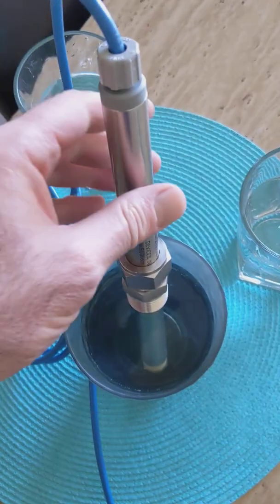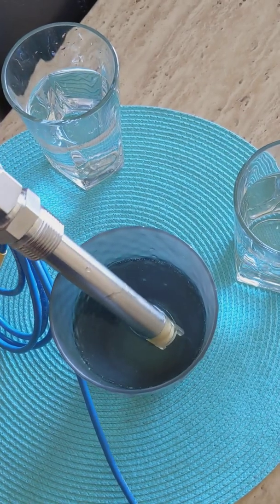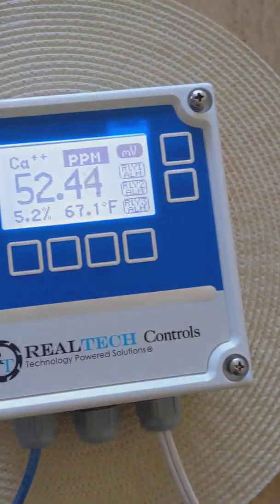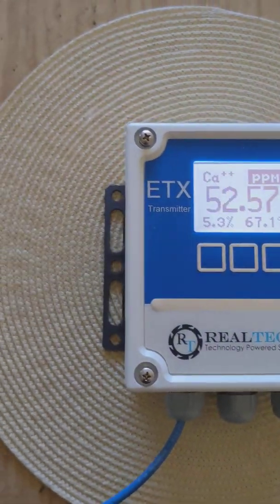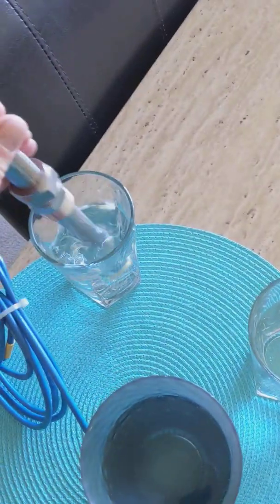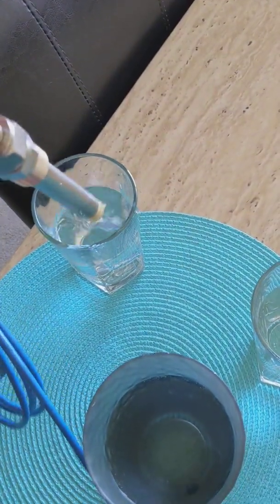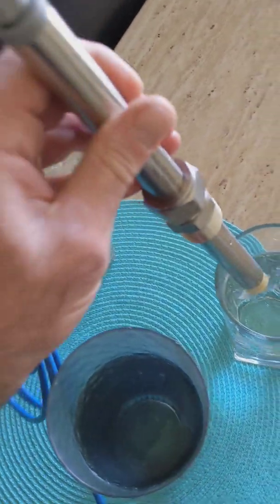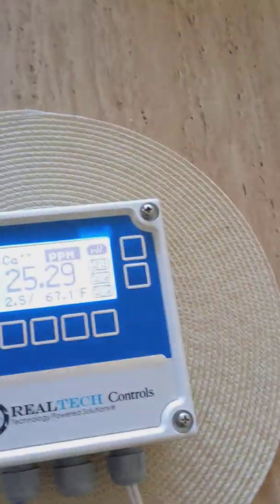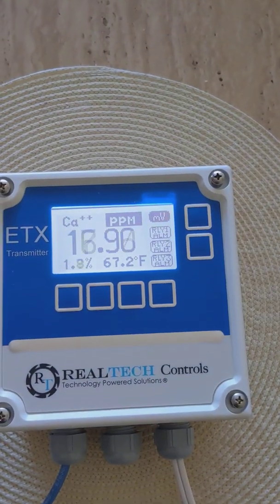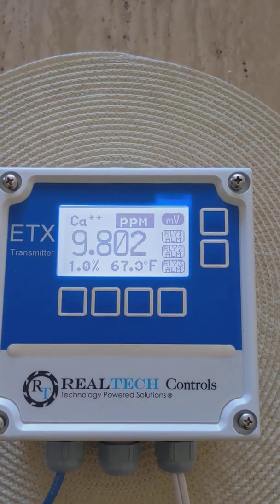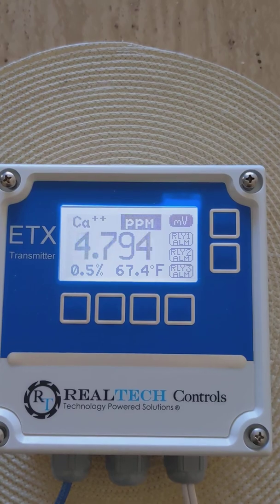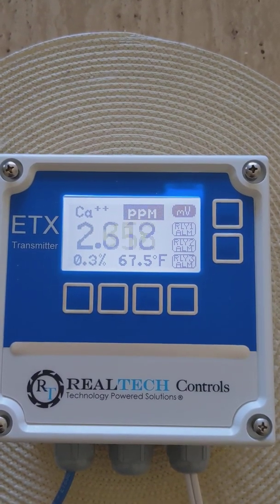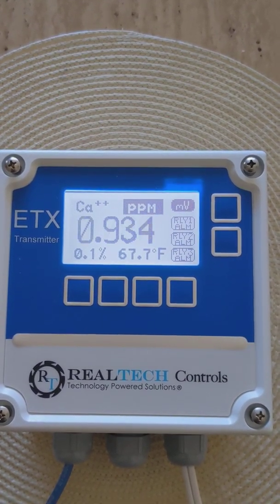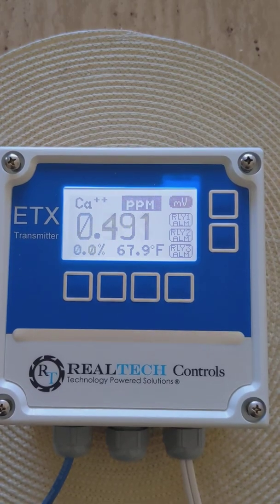I have my water hardness analyzer in city water, and it's reading 52 ppm. I'm now going to put it in distilled or deionized water. That's my rinse solution. Give it a bit of flow. And it's always a little bit of a challenge when you don't have the unit in process to get an exactly stable reading, but we'll deal in more or less.